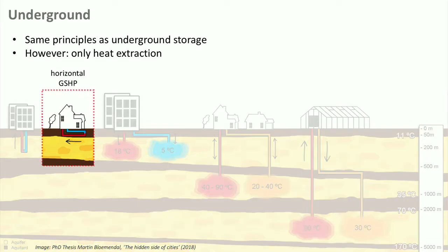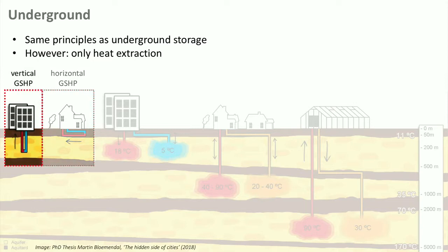Ground source heat pump systems use the top layers of soil and there are two types. Horizontal ground source heat pumps use a network of pipes close to the surface — 1 to 2 meters — and although they are relatively easy to build, they are more subject to seasonal changes. Vertical ground source heat pumps use one or more drilled shafts that go much deeper, up to 100 meters. This means a small surface footprint can deliver much more energy than a horizontal system, but drilling instead of digging is more expensive.